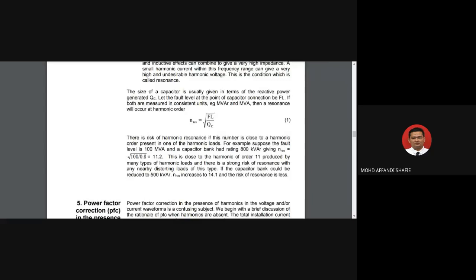Okay, so the size of a capacitor is really given in terms of the power generated, QC. Let the fault level at the point of capacitor connection be FL. If both are measured in consistent units, for example MVAR and MVA, then resonance will occur at harmonic order N_R. So there is a risk of harmonic resonance if this number is close to the harmonic order present in one of the harmonic loads. For example, okay, they've given the example here.